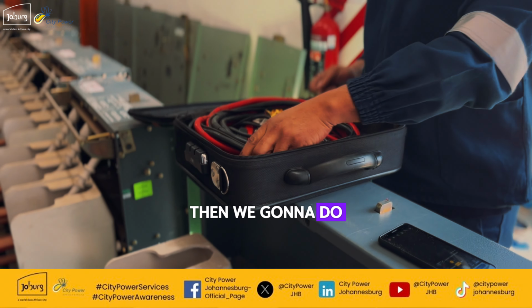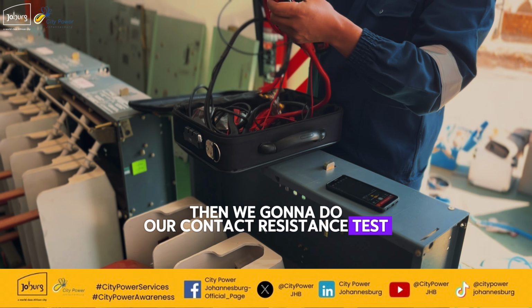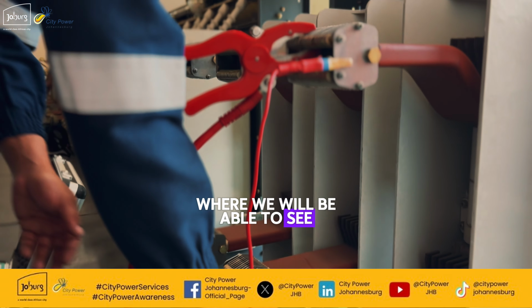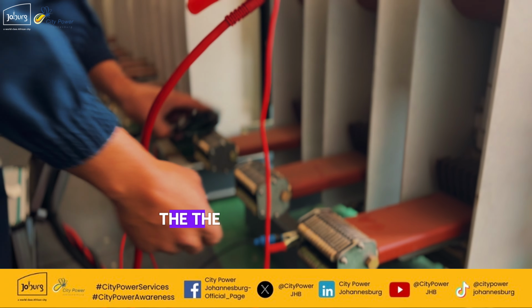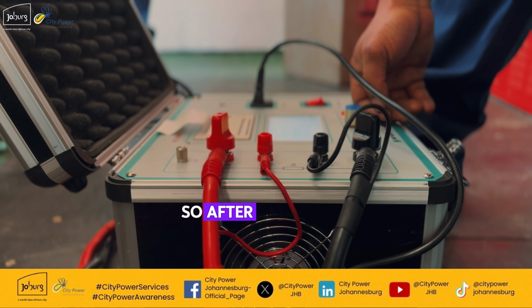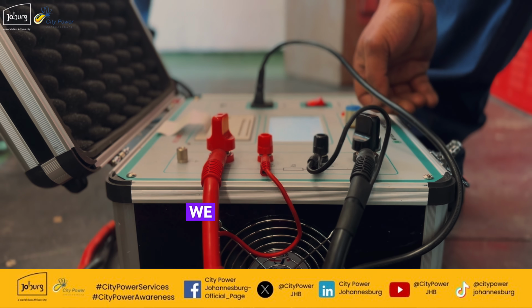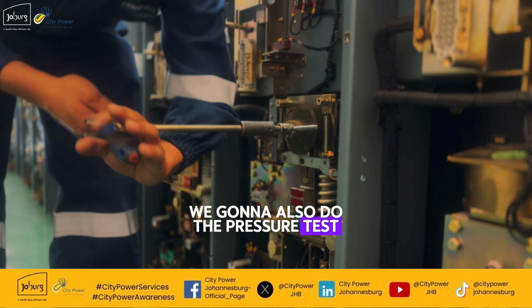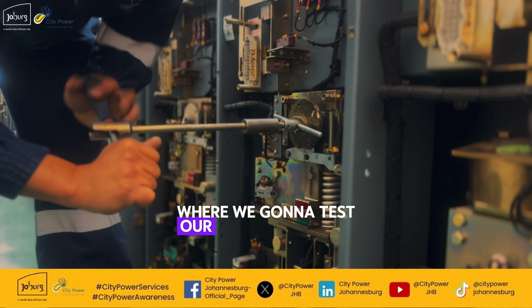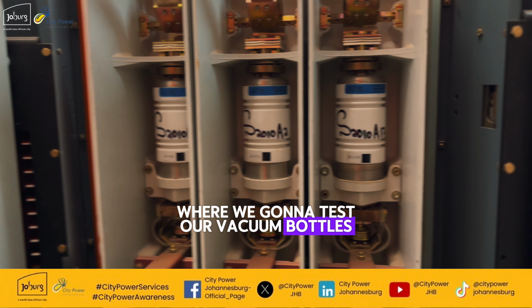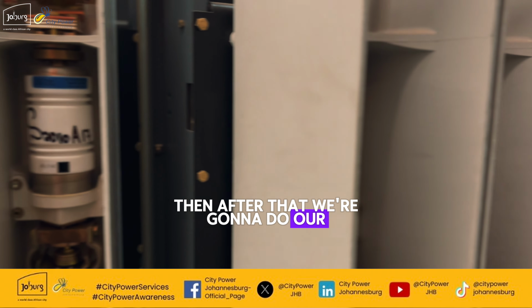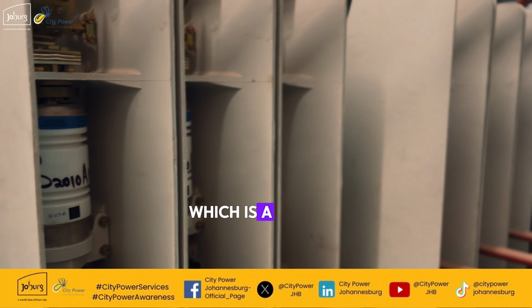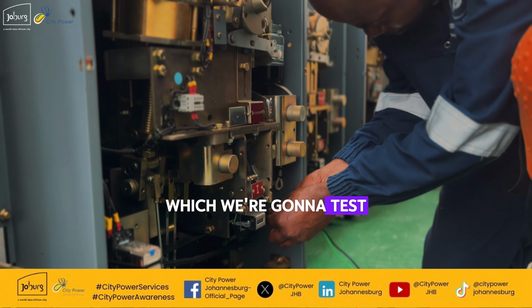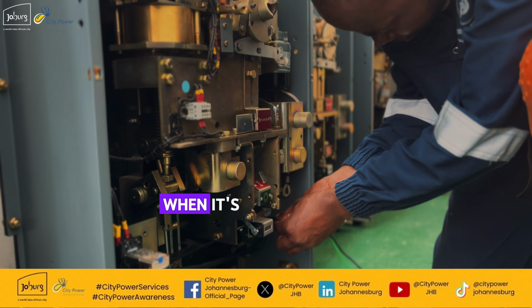Then we're gonna do our contact resistance test, where we will be able to see if it's making the correct contact. After that, we're gonna also do the pressure test, where we're gonna test our vacuum bottles. Then after that, we're gonna do our speed test, which is a breaker analyzer test, which we're gonna use to test the speed of the breaker when it operates.